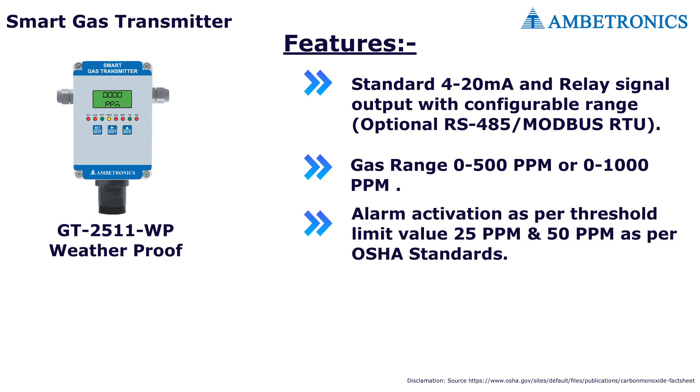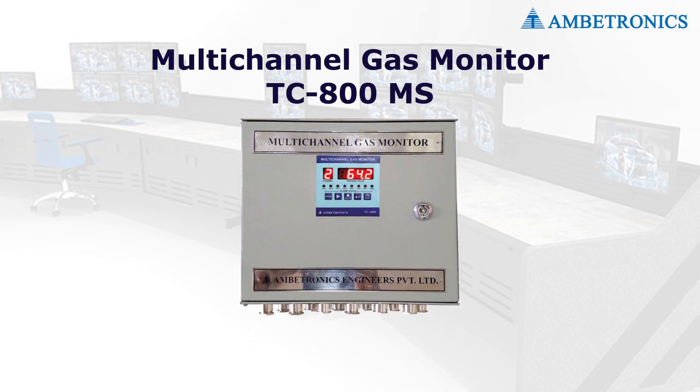The first alarm will be activated at 25 ppm and the second alarm will be activated at 50 ppm. Protection class is IP65. An LCD display is provided for ease of calibration. Ambetronics integrates all the gas detectors into a multi-channel gas monitor.